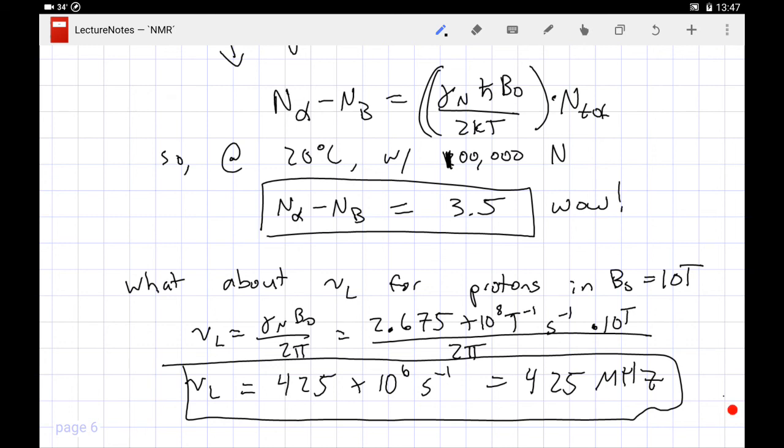So our NMR instrument is a 400 megahertz instrument, and what that specifies is roughly, not exactly 400 megahertz, but right around 400 megahertz to excite a proton, which means that our magnetic field is about 10 Tesla. Not quite, it's a little under 10 Tesla for us. But that's why NMR instruments are characterized by a frequency. That's the Larmor frequency, typically quoted as the frequency needed to excite a proton in the magnetic field of that instrument.